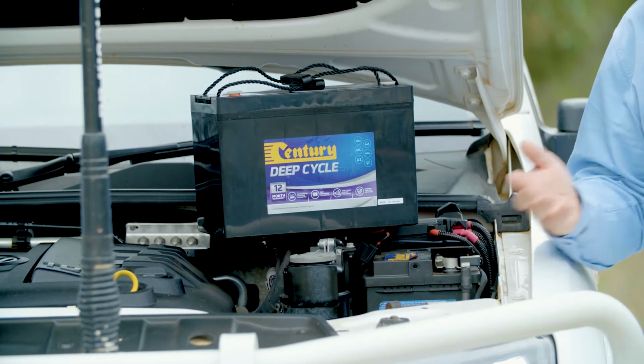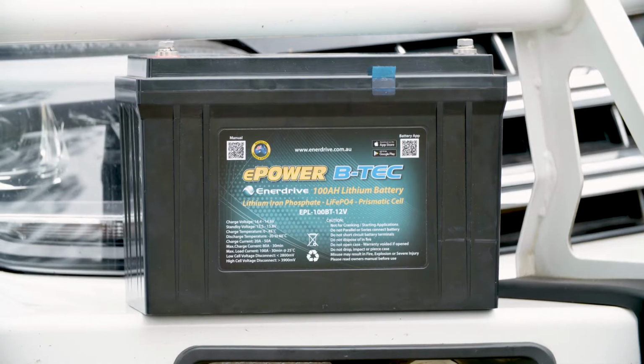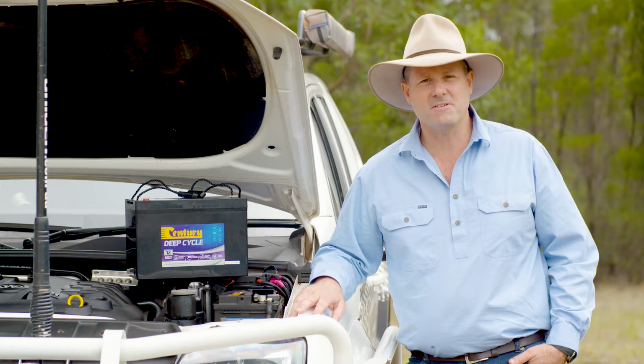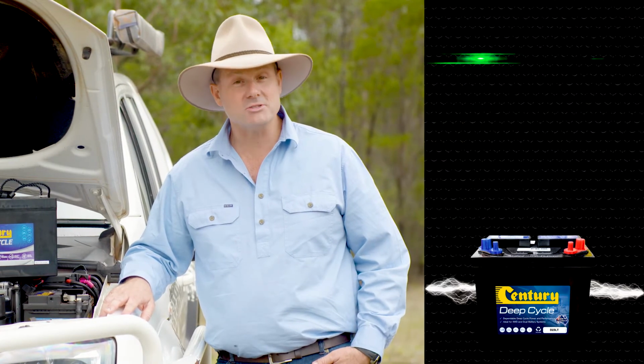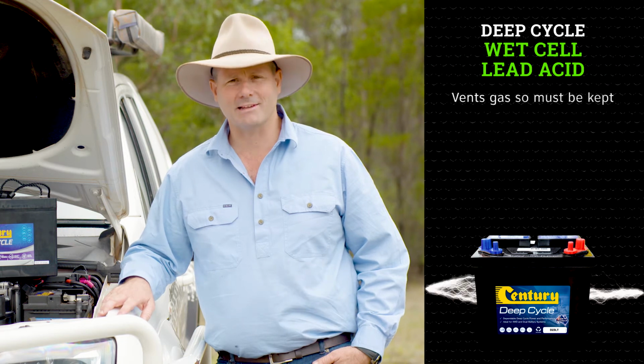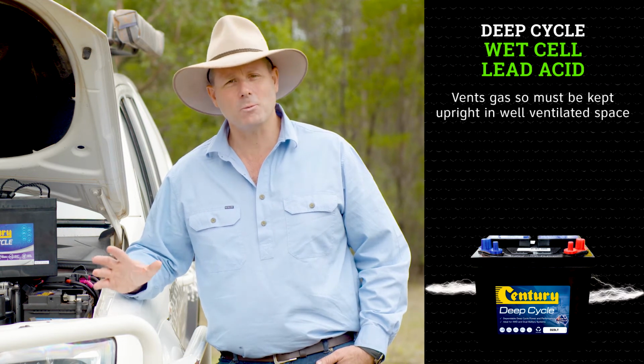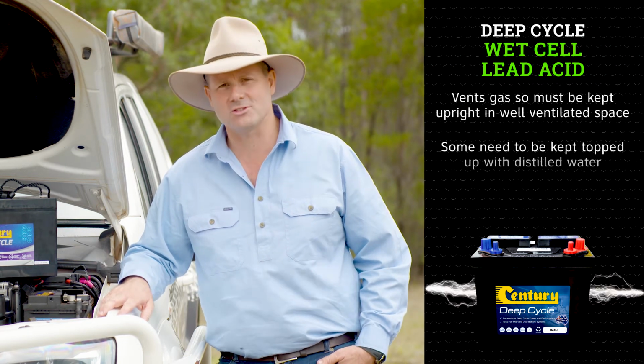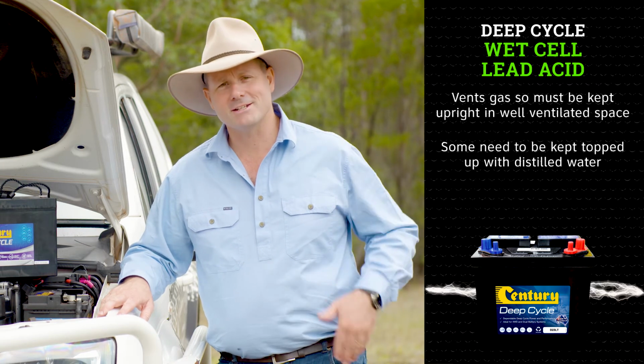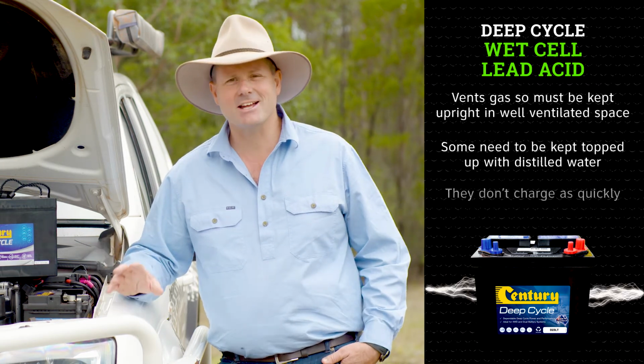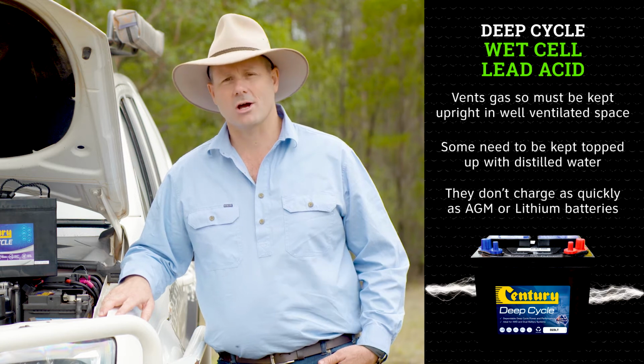Deep cycle batteries range from the inexpensive wet cell lead acid battery to the premium lithium battery. A wet cell lead acid deep cycle battery is the cheapest option, but it isn't always suitable. A wet cell battery vents gas to the atmosphere, so it must be kept upright and in a well ventilated area. You have to keep some wet cell batteries topped up with distilled water, although some are maintenance free, and they can't charge up as quickly as other deep cycle batteries.